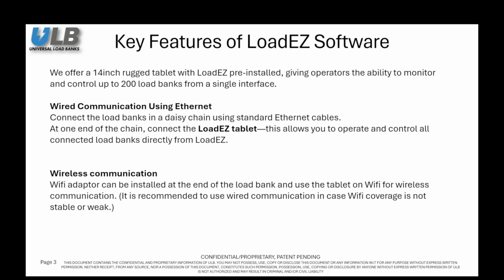Now let us talk about LoadEZ software features. We offer a 14-inch rugged tablet, and it comes with LoadEZ pre-installed, giving operators the ability to monitor and control up to 200 load banks from a single interface. For wired communication, simply connect the load banks in a daisy chain using standard Ethernet cables. At one end of the chain, connect the LoadEZ tablet. This setup allows you to monitor and control all connected load banks directly from the tablet.